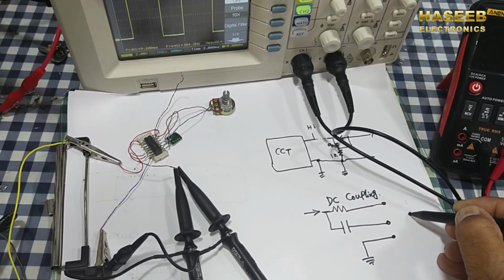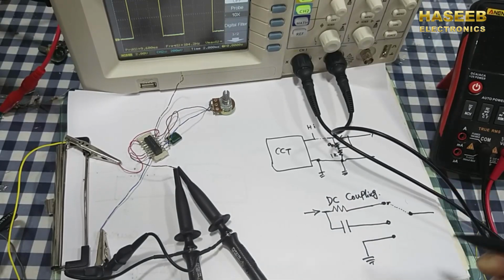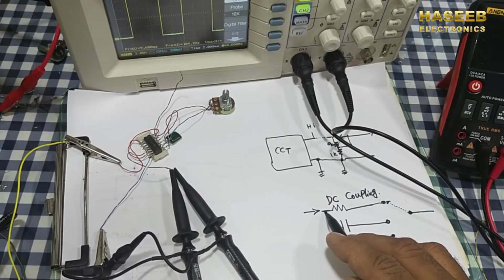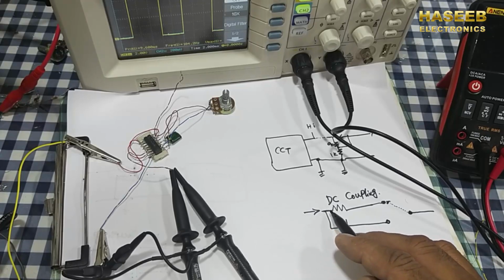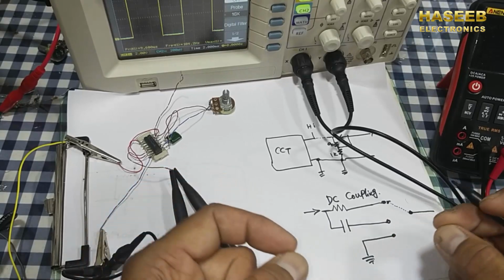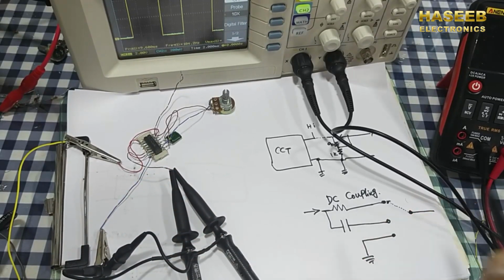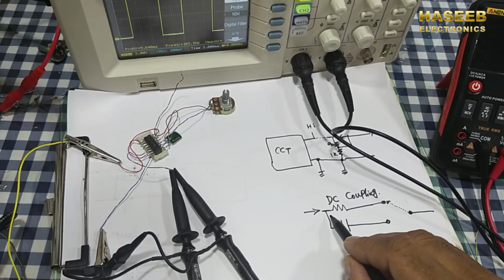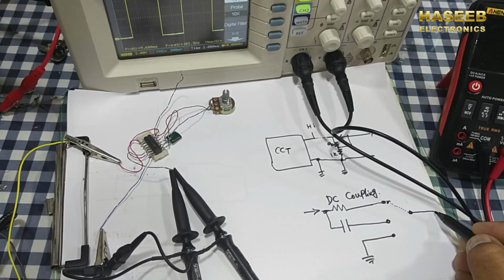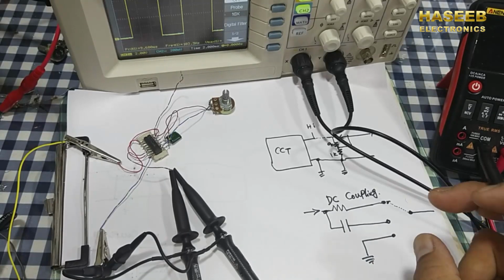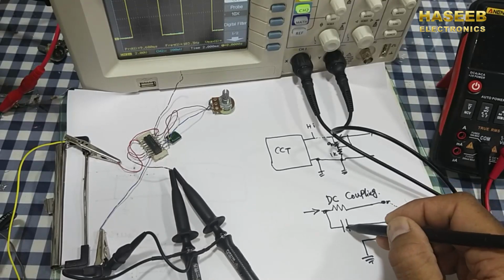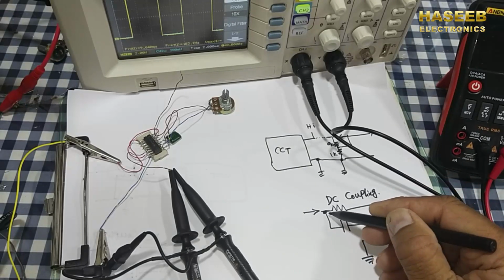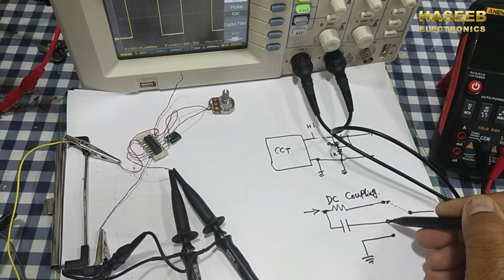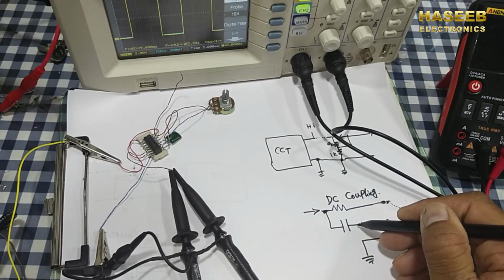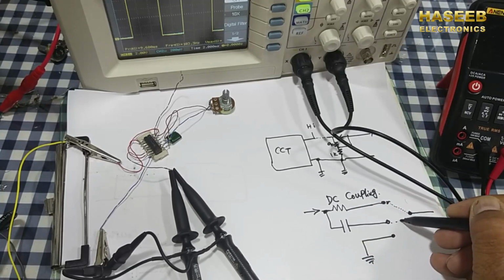If we select DC coupling, it will connect here. When we select DC coupling, the DC voltage containing any type of DC, AC, pulsating DC, any component of any type of signal will pass with the DC voltage. Either it is DC or AC, anything which is coming here will directly pass to the sample and hold circuit and to the processor. And if we want to test a purified AC signal, and we don't want to enter any DC component, any DC voltage to the scope, we have to pass through the capacitor. When it passes through the capacitor, it will couple here.